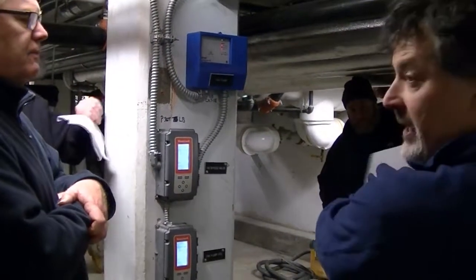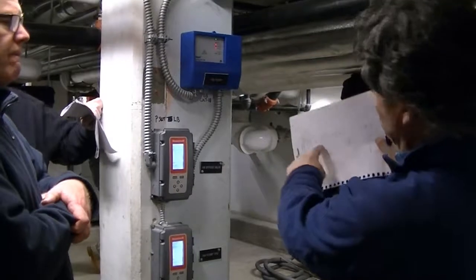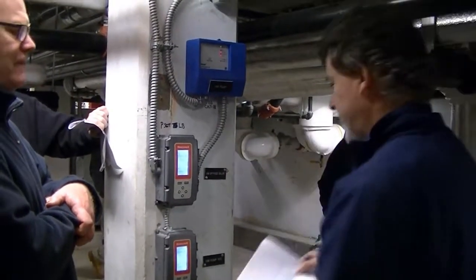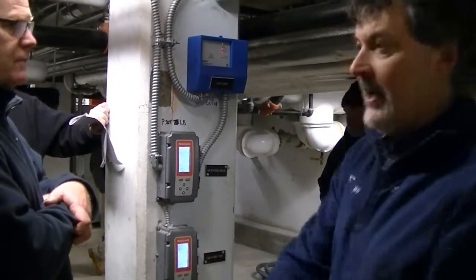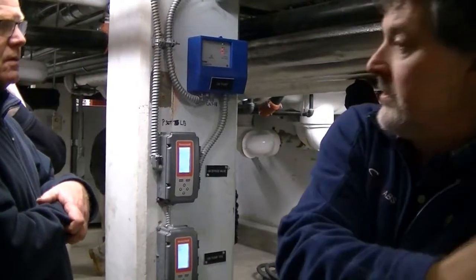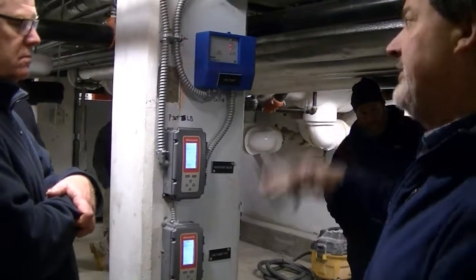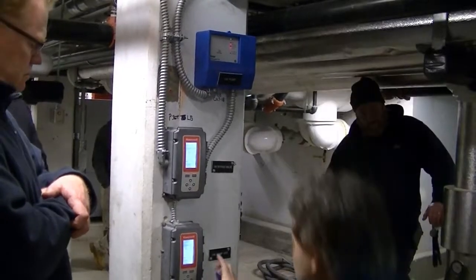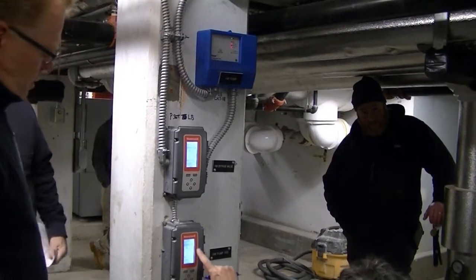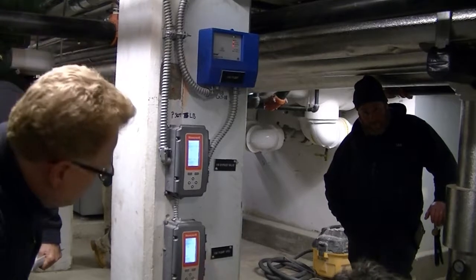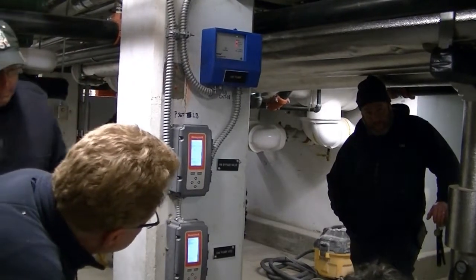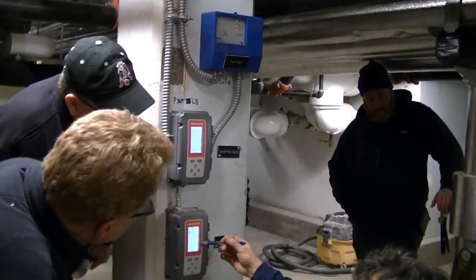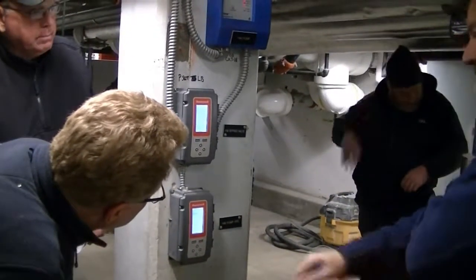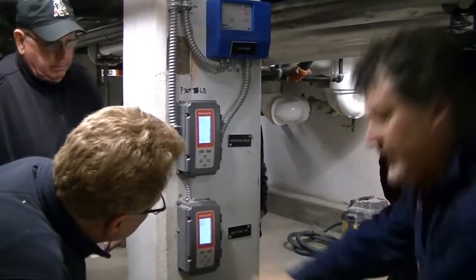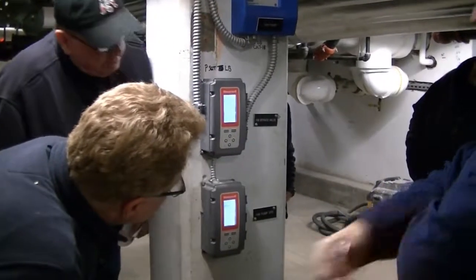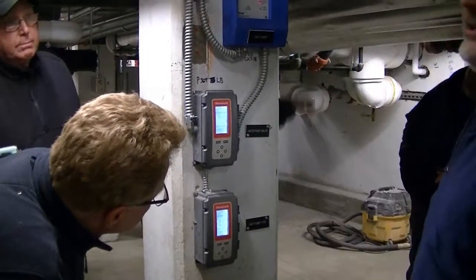So, differential pressure sensor, right now we got a 15 for the heat and hot water pumps, okay? So basically this controller sends a 0 to 10 volt signal to these two drives to modulate, to maintain that 15 right now, okay? Went down here, and if you hit the right arrow here, it will tell you what the set point is and what is controlling that. And it'll also say what it's modulating to. So if you just hit the right arrow, it'll tell you right there.